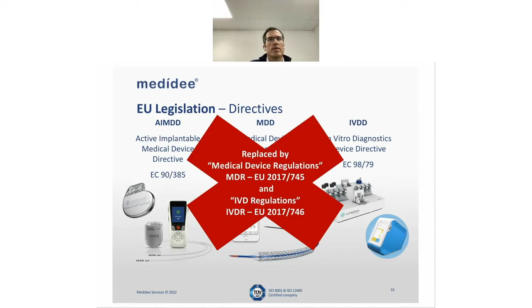You always need to take into consideration national law and other law at the European level, typically data protection. The General Data Protection Regulation is one regulation that is directly referred to from the Medical Device Regulation. So you have to take into consideration eventually new regulation. You'll see in the field of artificial intelligence that there is now a directive, which is a draft at the European level, which is a document that we will have to consider for medical devices as well. You have recommendations from the European Union, you have guidances, you have technical standards, and you also have best practices and so on and so forth. So at the end of the day, you have a starting point, which is the regulation, but it's never just one aspect that you have to take into consideration. It's a kind of puzzle of different items. And one of the challenges, of course, is to identify all the regulation you want to take into consideration.